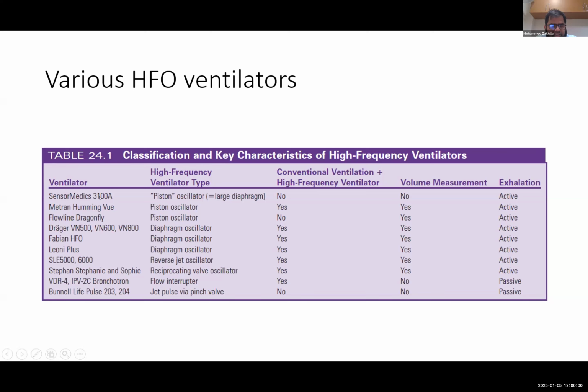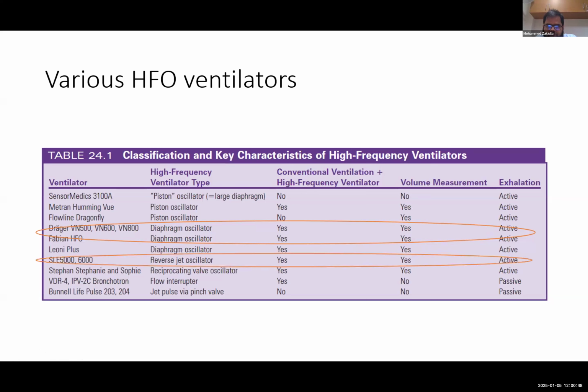Sensormedics is the standard standalone high frequency ventilator, but there are various others: Drager, Fabian, Leoni, SLE. These are hybrid ventilators where you can give both conventional ventilation and high frequency ventilation. There is also another ventilator, the Bunnell Life Pulse, which is predominantly used for high frequency jet ventilation. The basic mechanism of generating high frequency in Sensormedics is a piston, but Drager and Fabian use a diaphragm oscillator, that membrane, which determines your delta P and helps deliver this amplitude. In SLE, the mechanism is a reverse jet oscillator. In the expiratory limb there is a reverse jet, which helps deliver this delta P to the baby.